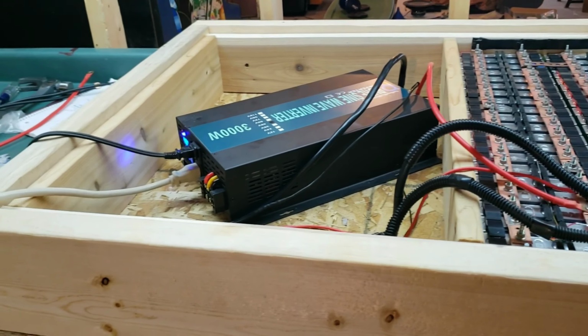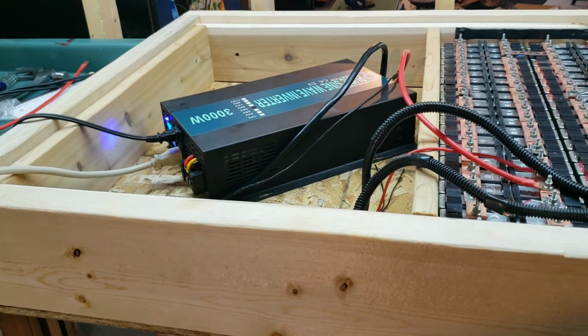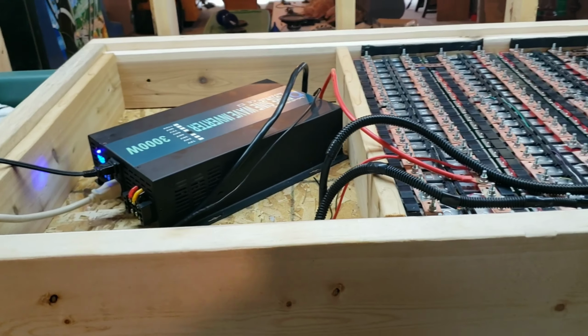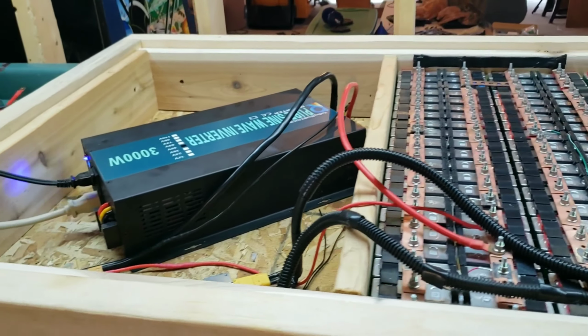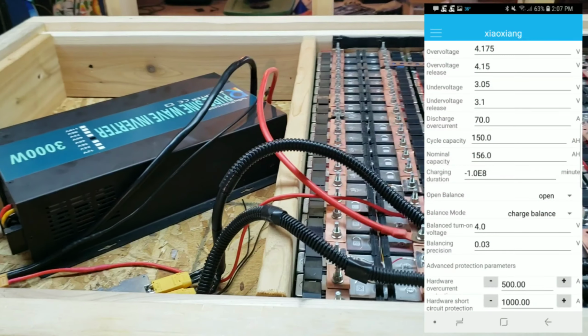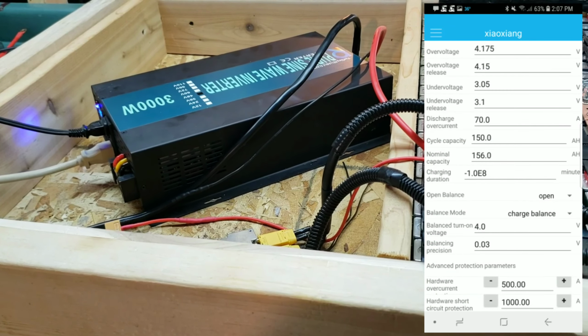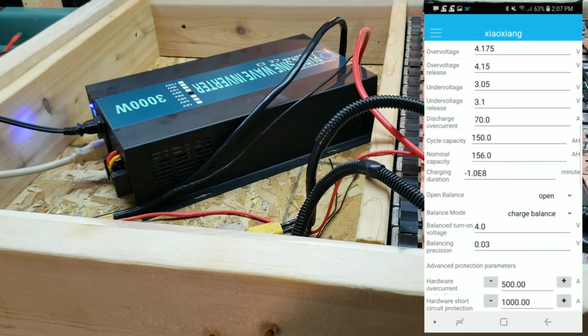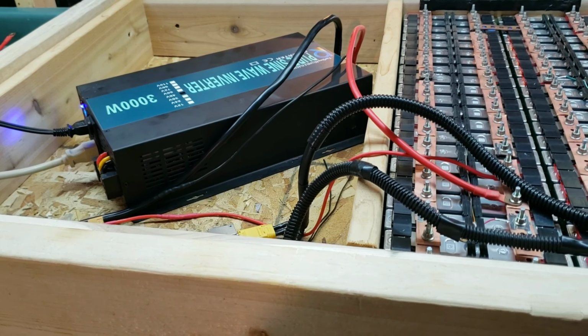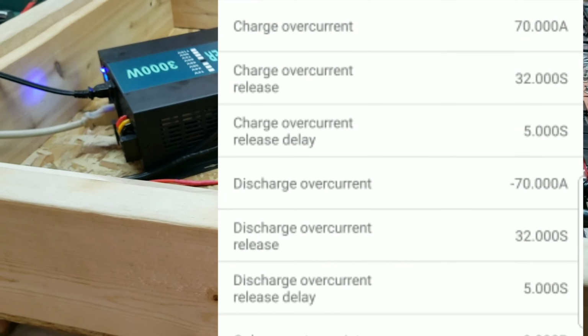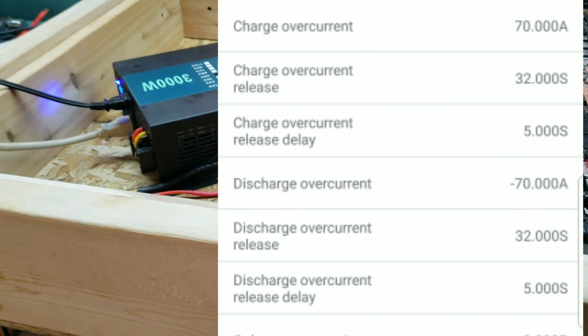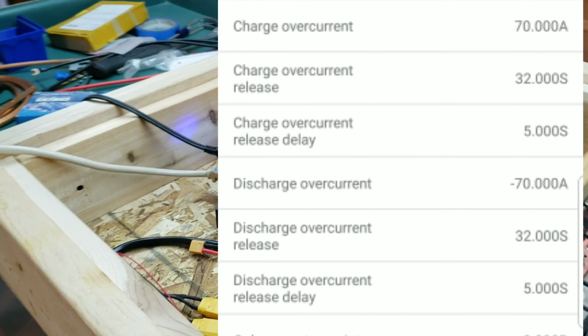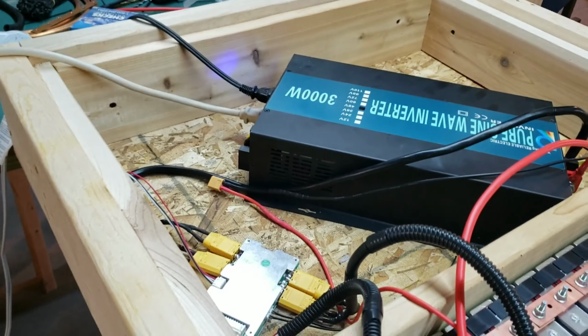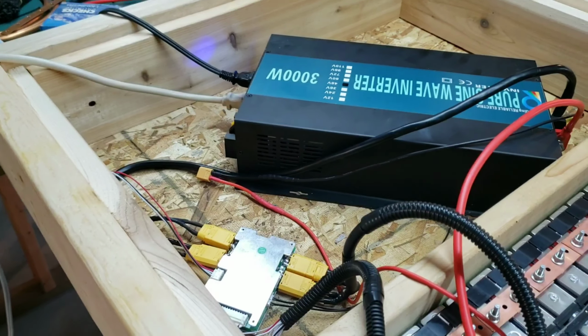Okay, real quick, I did confirm that the over discharge current is a value I can change within the app. It was set at 70 amps, with a cycle time of 32 seconds, meaning when it gets engaged the BMS won't turn back on for 32 seconds. That's why we saw it turn off and then turn itself back on automatically, all being done in the BMS.